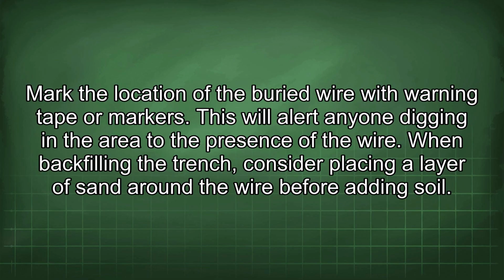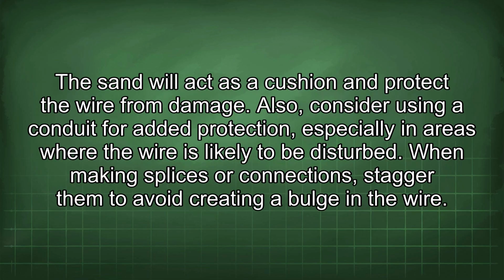Mark the location of the buried wire with warning tape or markers. This will alert anyone digging in the area to the presence of the wire. When backfilling the trench, consider placing a layer of sand around the wire before adding soil. The sand will act as a cushion and protect the wire from damage. Also, consider using a conduit for added protection, especially in areas where the wire is likely to be disturbed.